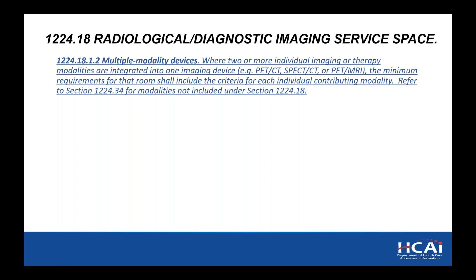And for MRIs, we added the requirements for safety zones. I'm not going to go through all the safety zones. Hopefully, if you've been doing MRIs, you understand safety zones are required. Zone 1 consists of the area for the general public, and as you get closer to the MRI equipment, Zone 4 is the strict area within the MRI scanner room itself. So again, this is a safety requirement for people having metal either in or carrying metal on their bodies. Those requirements have been there for quite a while, and now they're just being codified.